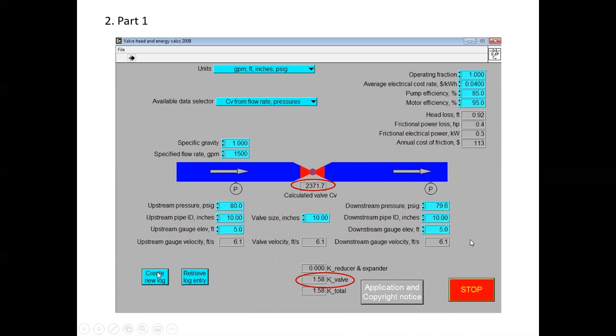Once you get used to using these things, they're so nice and quick, and they do a really good job. So anyway, if you call up valve tool, when you download PSAT, it comes in the same directory. It shows up in the PSAT directory. So you pull down your units and establish these. You figure out what we've got, 4 inputs. We've got upstream pressure, we got a CV on the valve, we got downstream pressure, and we got flow rate. So those are the 4. So you have to know 3, and then you just do the pull down menu to figure out what you want to calculate, assuming that you know the other 3. Well, we don't know the CV on the valve, but we know everything else.